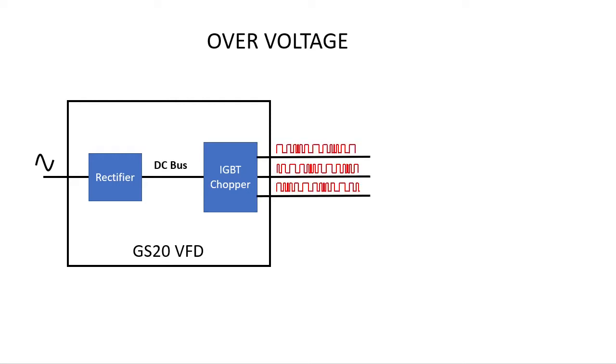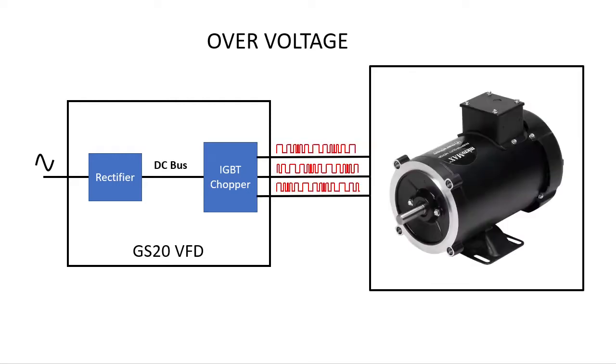Then it sends those chopped waveforms to the motor on three wires each with different phasing of the pulse width modulation. But when the chopped waveforms are used to slow a motor down, the inertial energy built up in the motor has to go someplace.